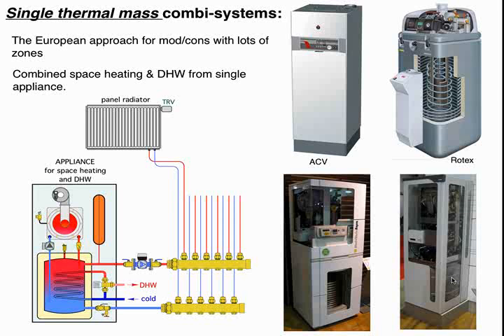Here's another one from a different company. Again, you'll see an insulated small tank, probably on the order of 20 to 25 gallons in the bottom of these appliances. And the concept is shown over here. What they're doing is they're basically using a modulating, condensing heat exchanger, as we would have in a wall-hung boiler, and they're sending that heat down into this insulated tank. The tank then connects out to a space heating distribution system, but it also has a coil heat exchanger. Typically, it's a corrugated stainless steel coil, generously sized, so there's a lot of surface area.